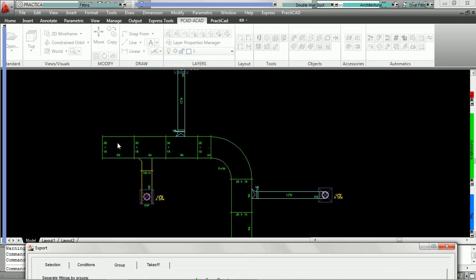The green duct happens to be drawn with a 6 inch water gauge specification — this is going to represent our high pressure group. The yellow duct was drawn with a 2 inch water gauge specification — this is going to represent our low pressure group. And the blue duct happens to be under the fabrication level order only, because this duct we're buying and we'd like to order it. So we'd like three groups: high pressure, low pressure, and order.